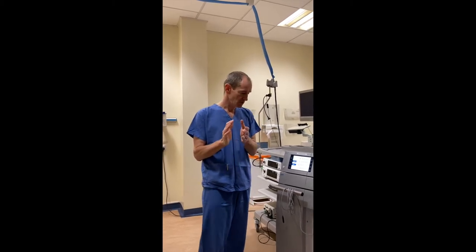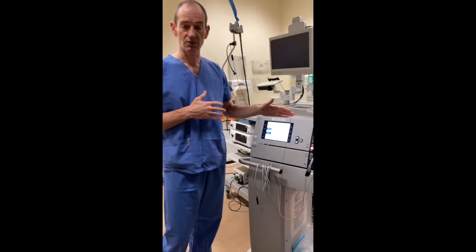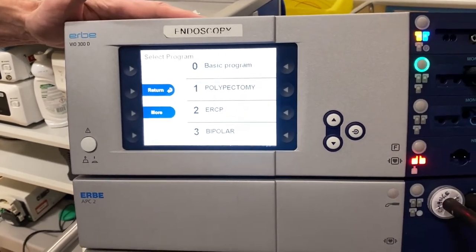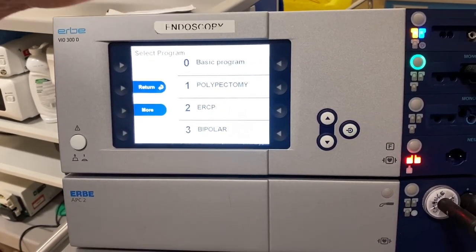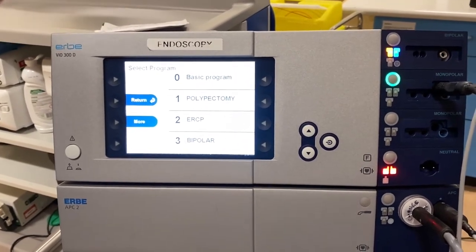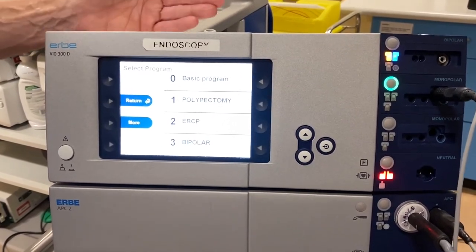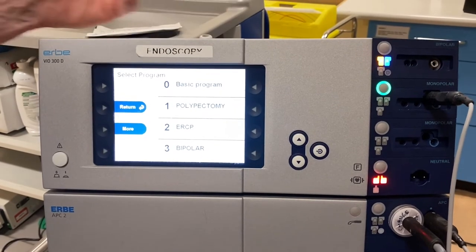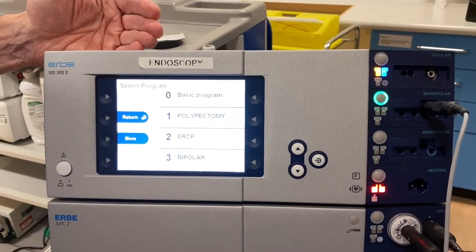A little bit of theoretical knowledge is essential. Now I'm going to show you the machines that we use. There are lots of these available — I'm just showing you the Erbe VIO 300 model, which is commonly used in endoscopy. But you've got to be aware that there are lots of different manufacturers and models of generator available, and it's imperative that you're familiar with what's available in your unit. Your unit may have more than one type, or if you scope in more than one hospital or centre, they may have different generators that don't all set up and behave in exactly the same way.